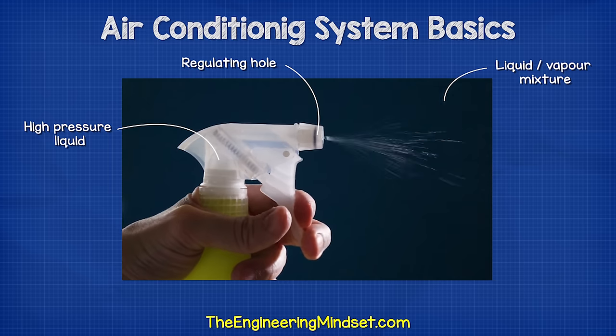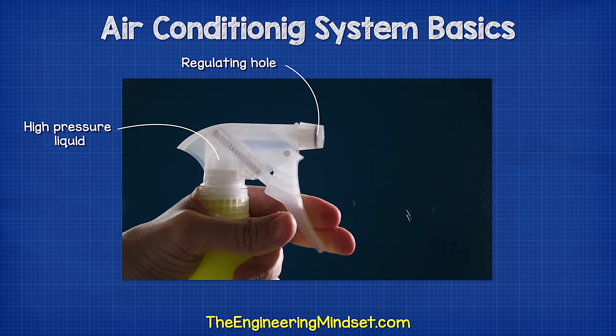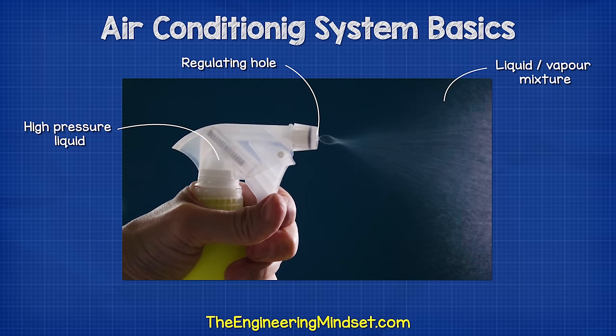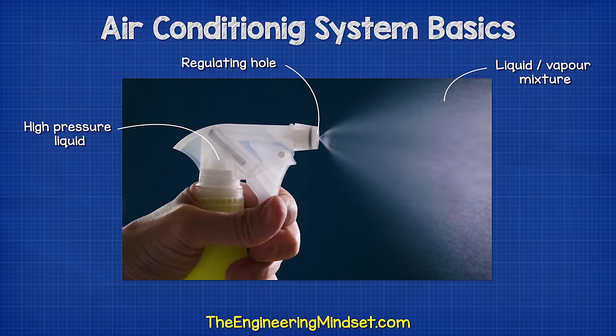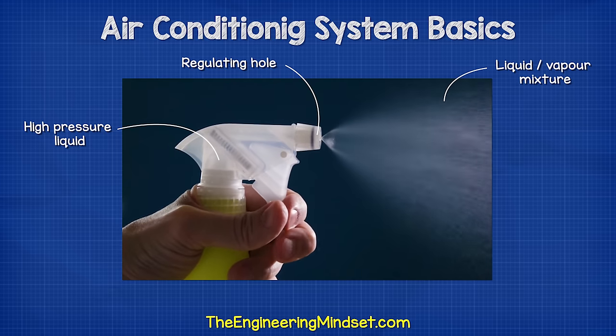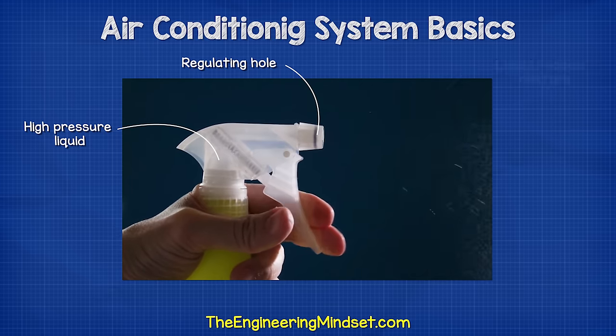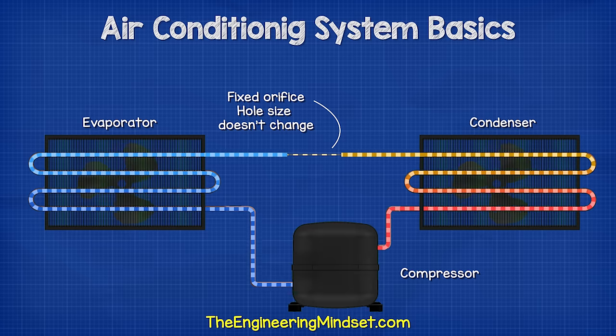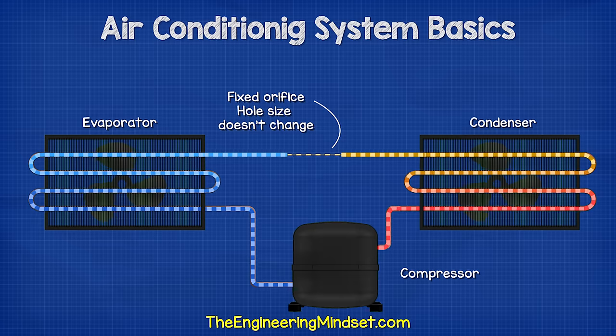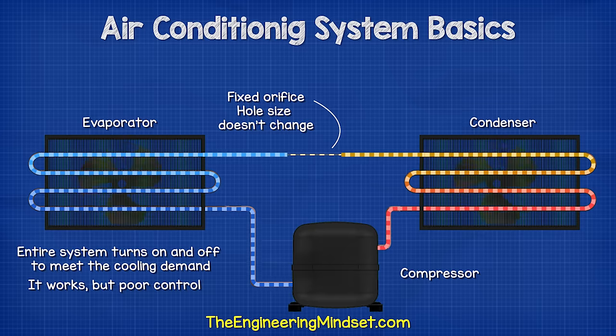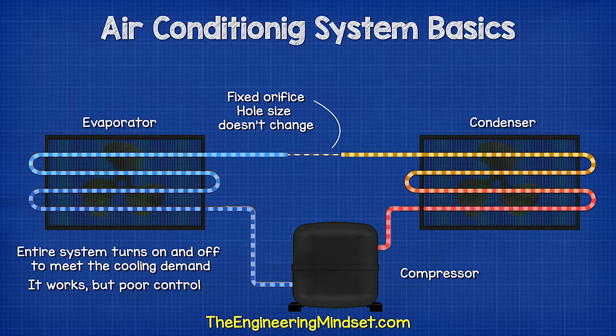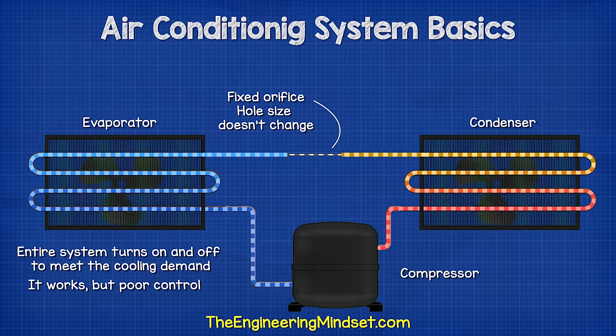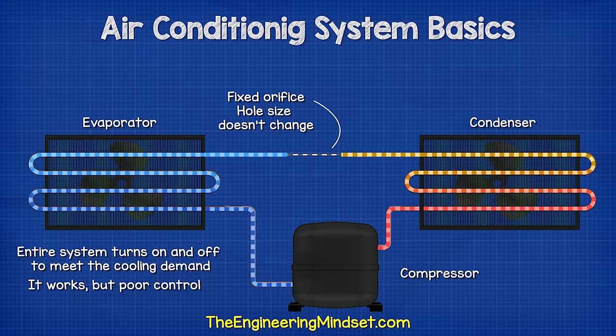It's a little bit like spraying a deodorant can or a spray paint can — it flows through a small hole, causing it to expand as a part vapour and part liquid mixture, and then we can feel the can become cooler. The original method to control this was by using a fixed orifice device, and you might still find these on the back of your refrigerators. The hole within this device was a fixed size, so the entire system would simply turn on and off to meet the cooling demand. It does work, but we can't maintain a stable temperature control because the system is simply turning on and off.